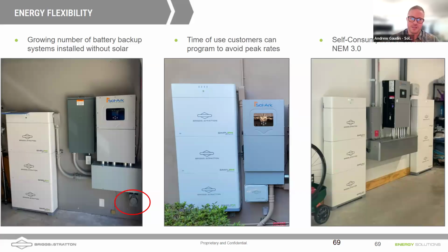Yeah, or I'd say if the only generator that would ever be hooked up to it would not have a 2-wire start, you could potentially keep the Gen Force option enabled. That way, when that generator is plugged in and you start it up, the Sol-Ark will look to synchronize with it and accept power.